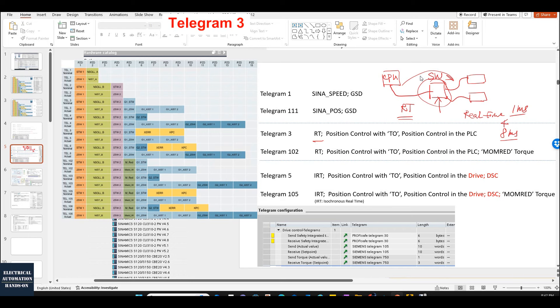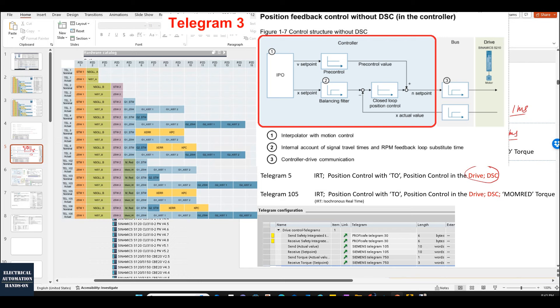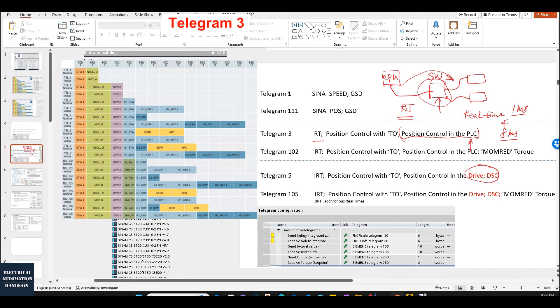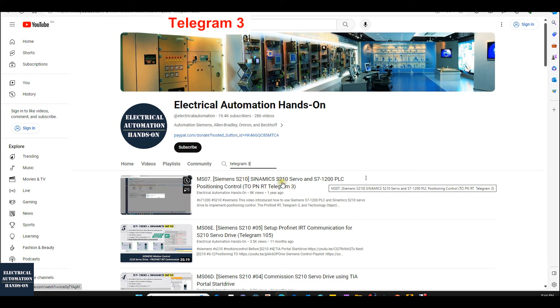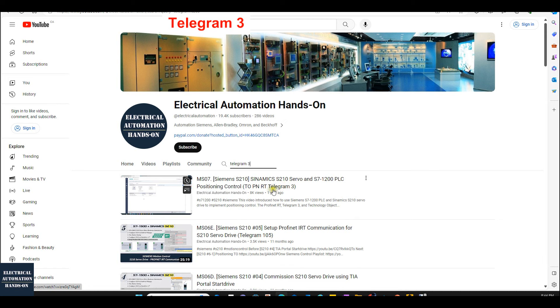However, when we set up RT communication we lose the DSC function performance. This makes the closed loop controller locate in the PLC. You can imagine: if your PLC plays the role of positioning controller, your drive only acts as the speed controller. This makes your PLC workload much higher — your PLC becomes very busy. For example, I showed in one video how to use the Siemens S7-1200 PLC to communicate with the S210 servo drive using telegram 3.